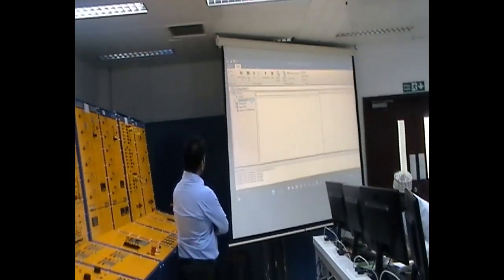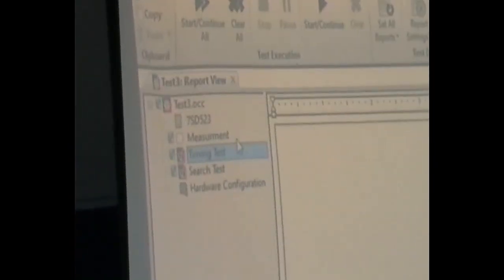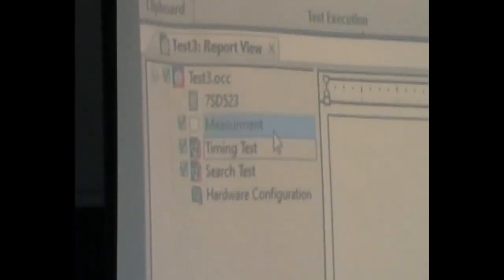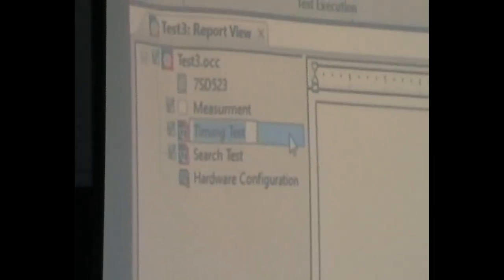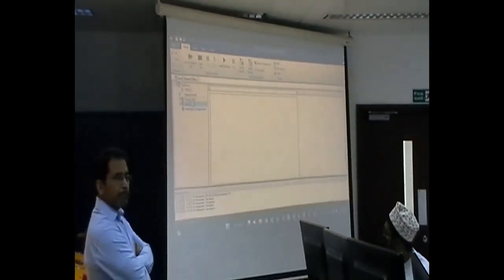If we've continued it all without stopping, it will show me a green mark for the test, either pass or fail. But we'll do it for the timing at least. Now I have two tests. I want to check the reach of the distance relay in each zone, and I also want to check the time. First we'll start with the timing test.